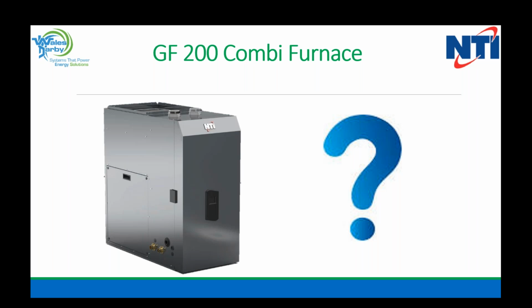And you'd only be at the maximum temperature you'd be running out there, Jim. They don't really run more than 160-degree water out there in order to achieve that 97% efficiency. So, you know, that would also make it condense, which is good. But that would be a couple of your obstacles. But you know, where there's a will, there's a way. It's water, right? We can do pretty much anything we need to do with hot water. Even if we took it off the outlet side and ran it through a plate exchanger or something, you could always put a zone off of that.